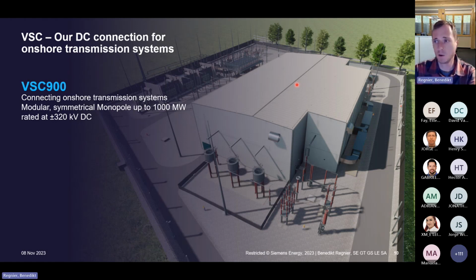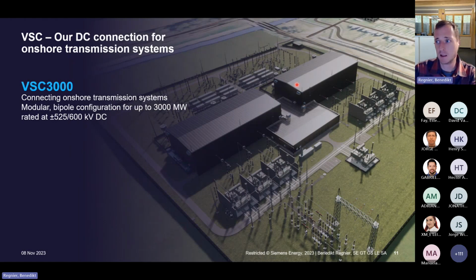I said this is the symmetrical monopole solution. And the biggest we would have is the VSC 3000. This is a VSC solution in the bipolar configuration up to 3000 megawatt. So meaning 2 times 1500 megawatt at a voltage of plus minus 525 kV DC, or also possible plus minus 600 kV DC. Here in the example, a lot of stuff is outdoors. We can do this if it's possible with the authorities and if the environmental conditions allow for it, then of course it's the most cost optimized solution.